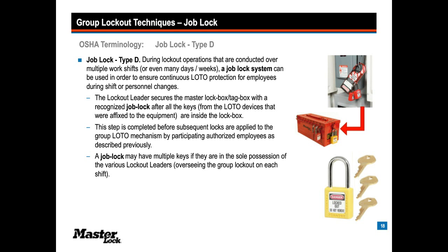Now in this situation, the lockout leader secures the master lockbox with a recognized job lock after all the keys from the lockout devices are inside the box that is securing the machinery. This step is completed before subsequent locks are applied to the group box, meaning that we're getting the participation of workers who are going hands-on.